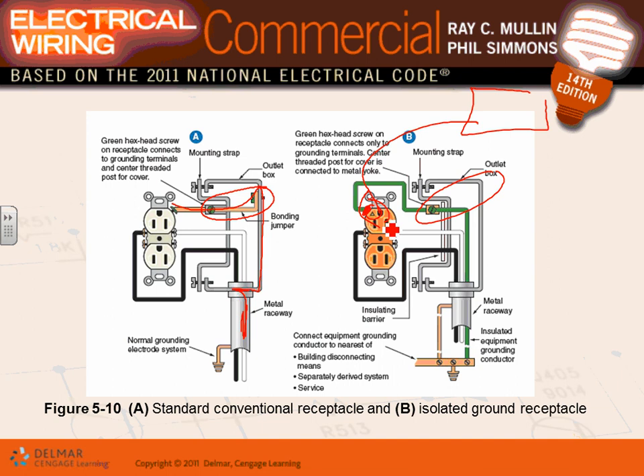Any comments, any questions, Derek, my friend, about isolated ground receptacles? So in all the technology circuits, we call them technology circuits that we're going to have, technology receptacles. In this project, they are asking you for the requirement about isolating ground receptacle. You hear this all the time. Unless they tell you it's an isolating ground receptacle, you do not specify an isolating ground receptacle.